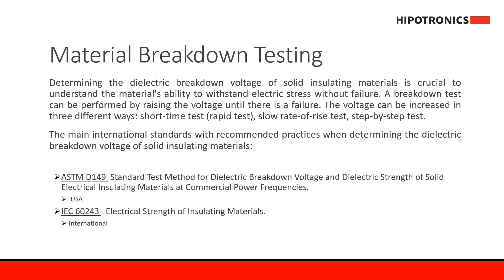For material breakdown testing, determining the dielectric breakdown voltage of solid insulating material is necessary to understand the material's ability to withstand electrical stress without failure. The breakdown test can be performed by increasing the voltage until there is an actual failure of the insulating material. The voltage can be increased in three different ways: the short time test, which is a rapid test; a slow rate of rise test; and a step-by-step test.